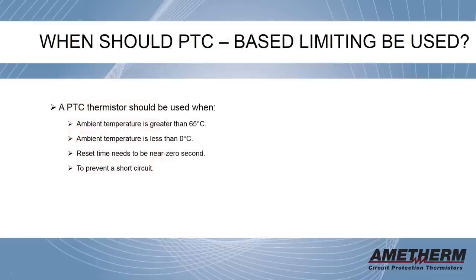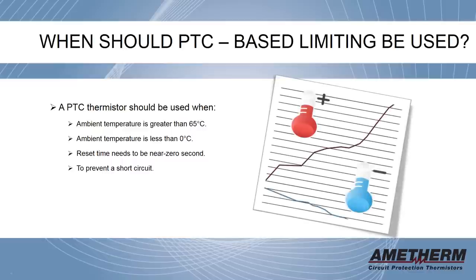When should PTC-based limiting be used? A PTC thermistor should be used when ambient temperature is greater than 65 degrees Celsius, ambient temperature is less than 0 degrees Celsius, reset time needs to be near 0 seconds, or to prevent a short circuit.